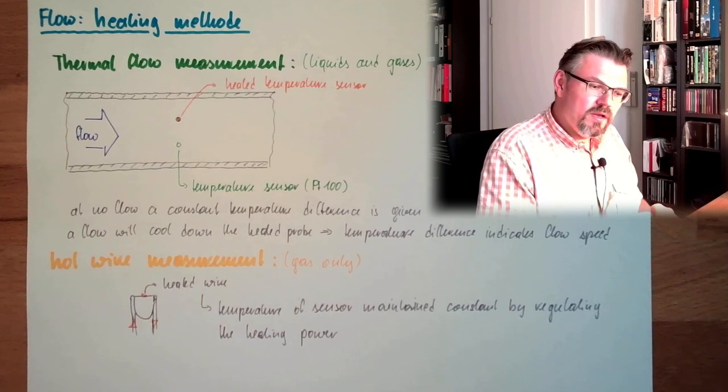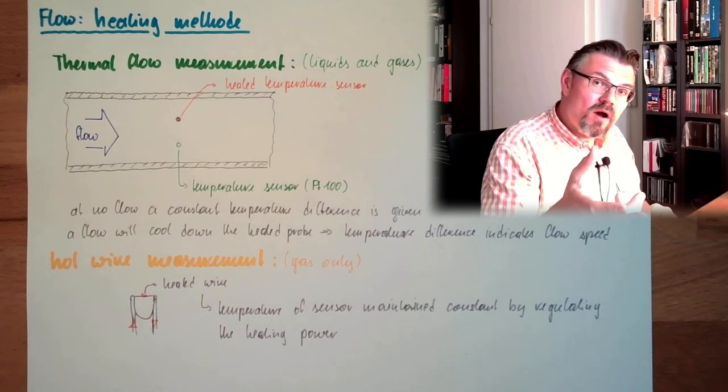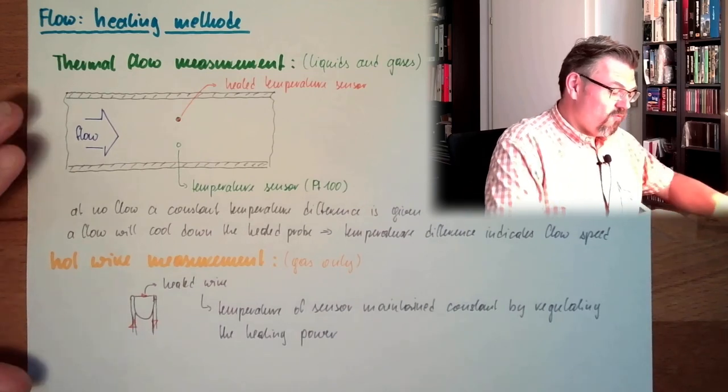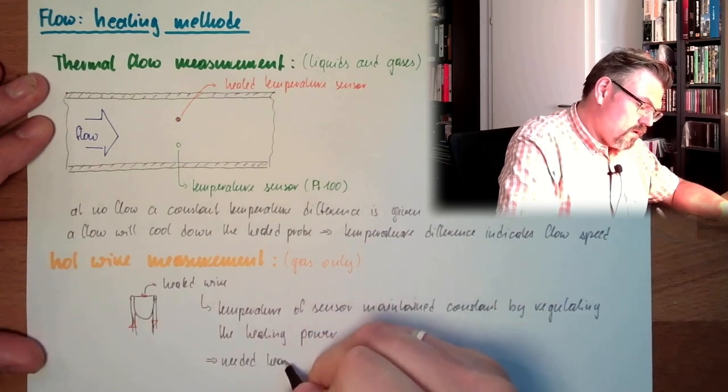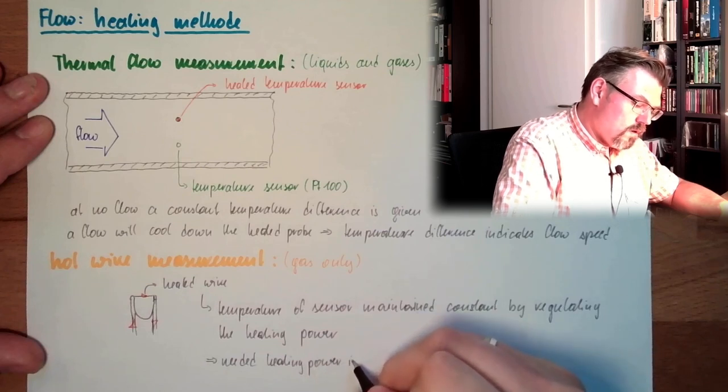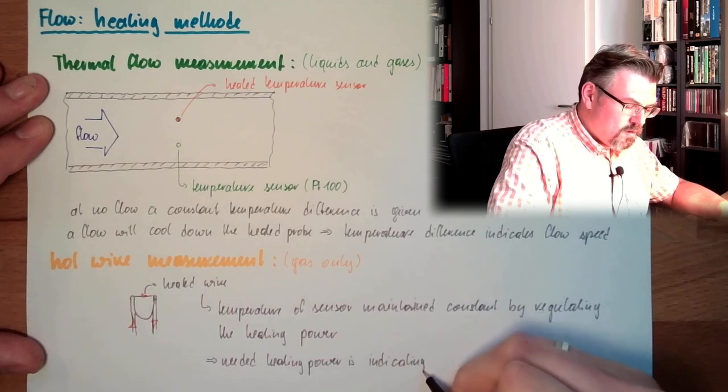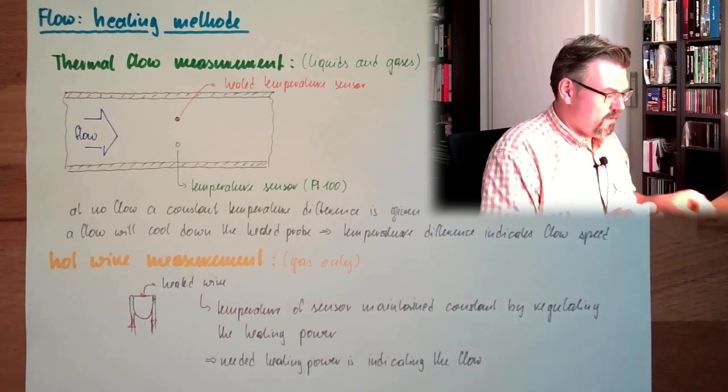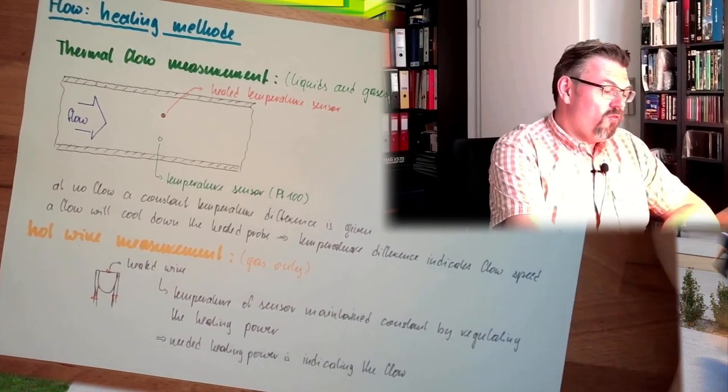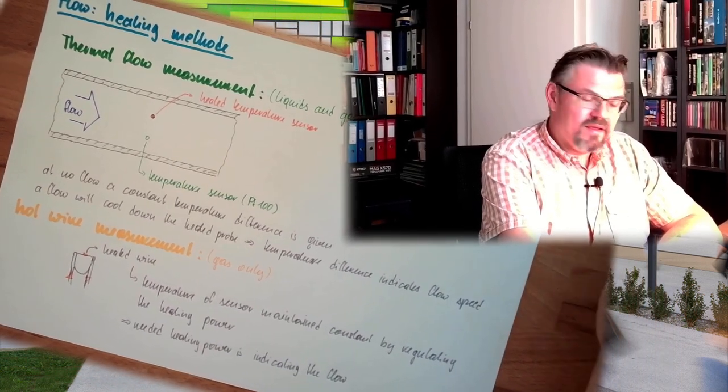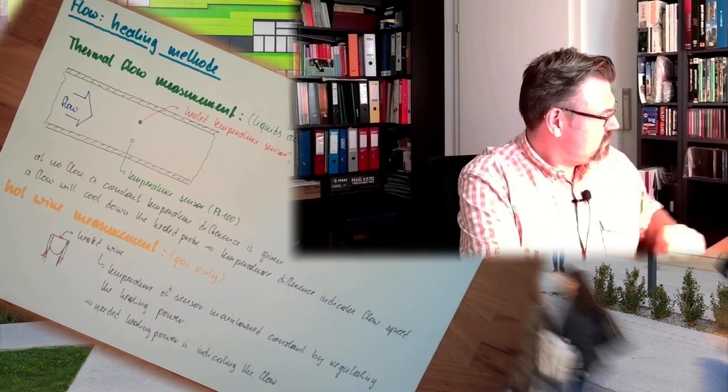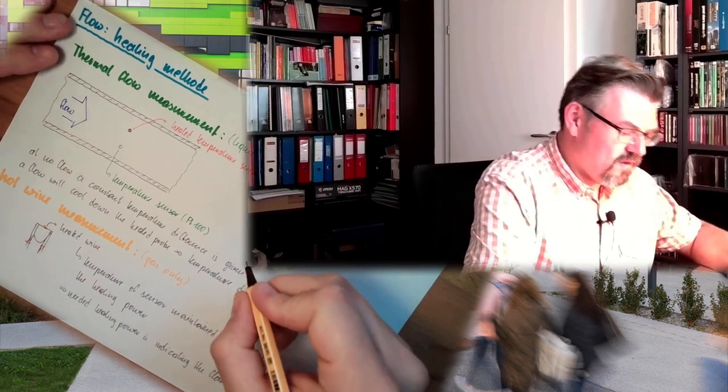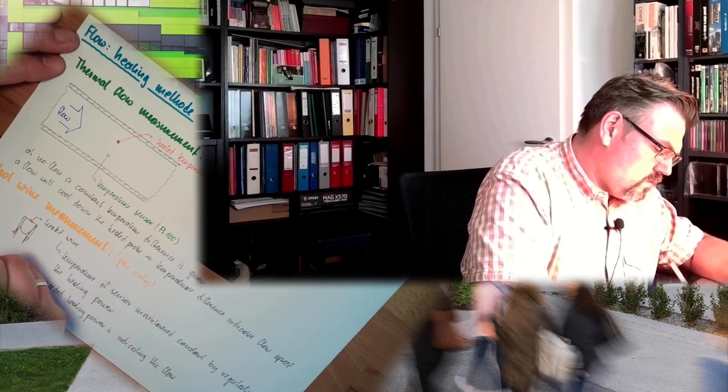Actually what we do is we look at the needed heating power, and the needed heating power is reflecting the flow. So the needed heating power is indicating the flow. These are thermal flow measurement, hot wire flow measurement, heating methods I call it, these two things. The accuracy is around 1 to 1.5 percent of the value. These things here are already measuring not only the flow, they are also measuring the mass.